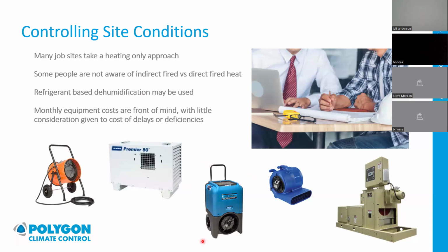A refrigerant-based dehumidifier, like this blue one here, is what you'd see if your basement flooded and you called a restoration company, like Polygon, which does restoration in much of the world. They'd bring a handful of these over along with some fans to help dry the place out. This is a refrigerant-based unit, essentially an air conditioner with a heater. Air flows over the air conditioning coils, cools down to a saturation point, and water falls out of the air, drips through a line, and gets pumped out. Then the air gets reheated so it's usable. That's a refrigerant unit.